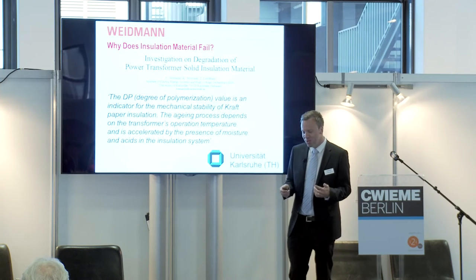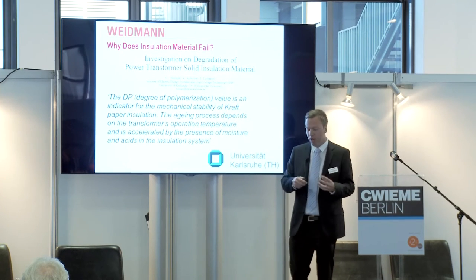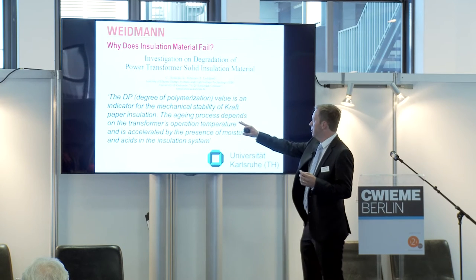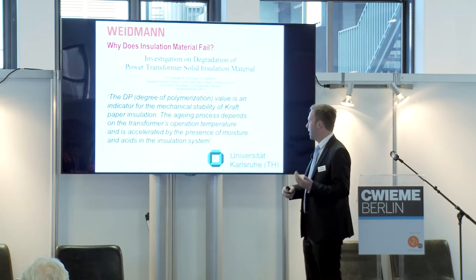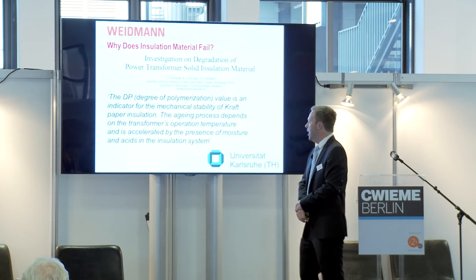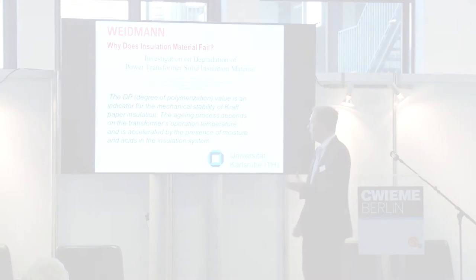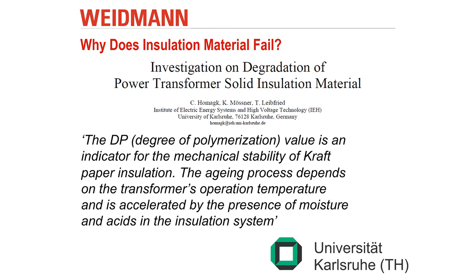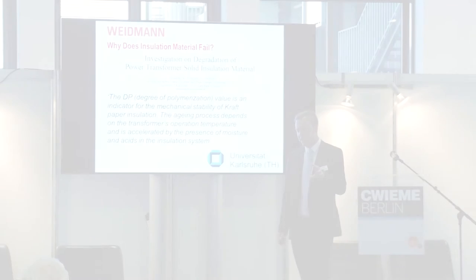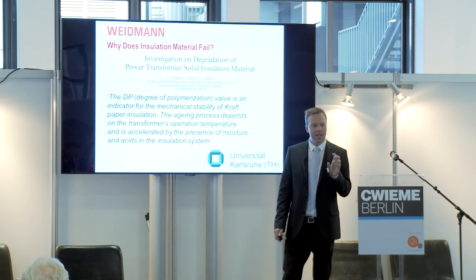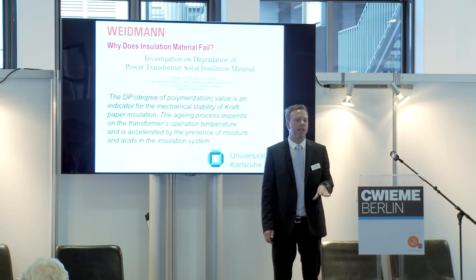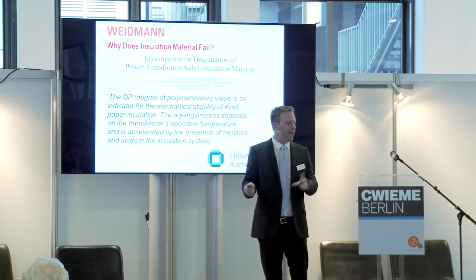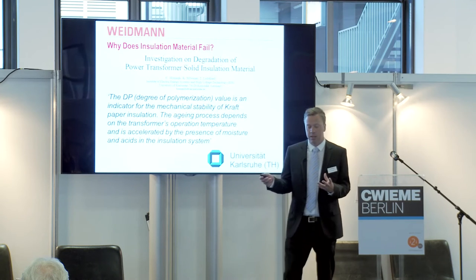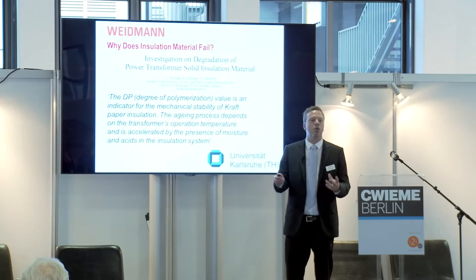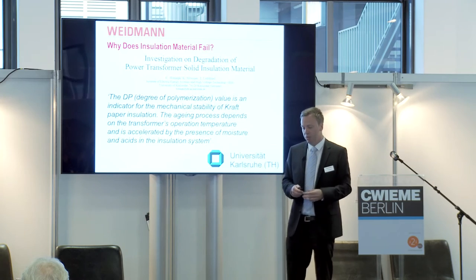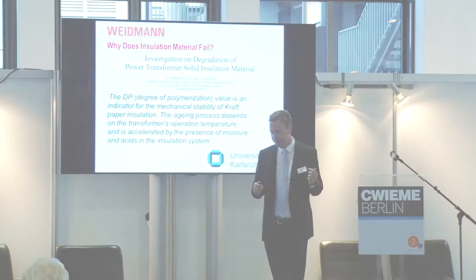The University of Karlsruhe states, in an investigation of breakdown of insulation, that the degree of polymerization value is an indicator for the mechanical stability of kraft paper insulation. This is a direct look at the aging process of the insulation package in the transformer. They state that the presence of moisture in the insulation system is a key driver for the breakdown of insulation. So the key takeaway is that moisture in the insulation is a key driver of the aging process and reduces the degree of polymerization.